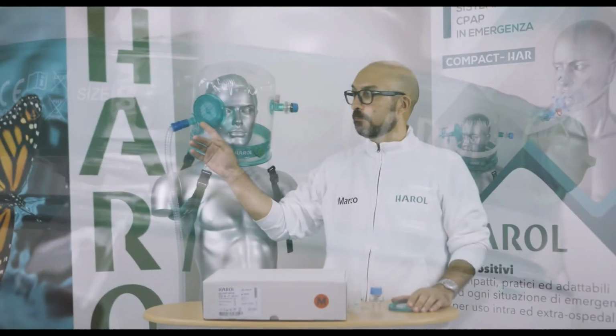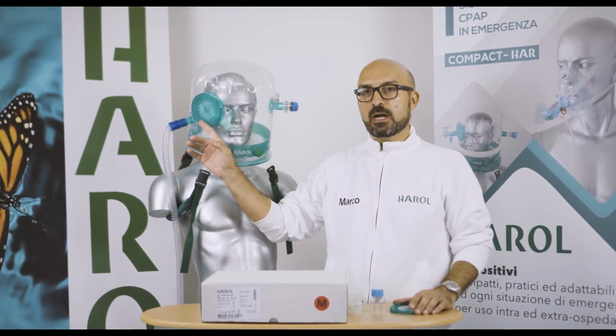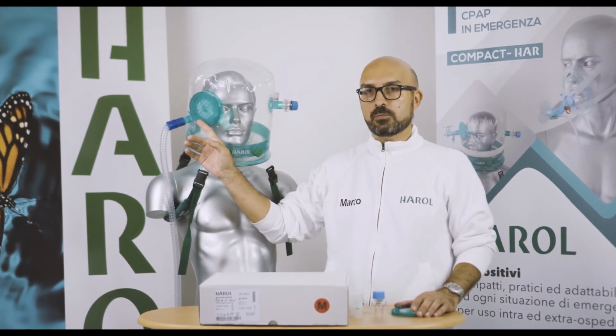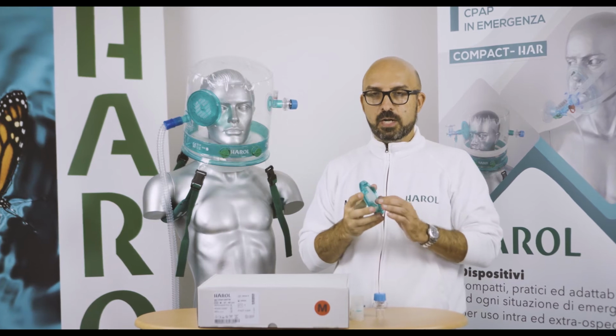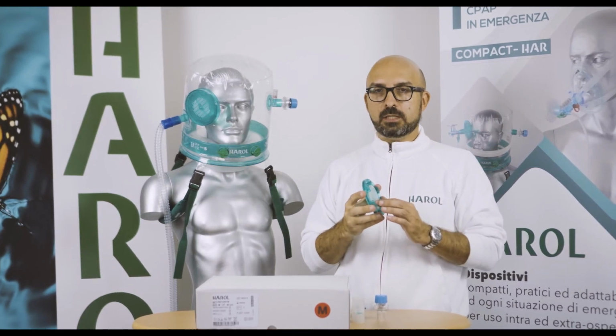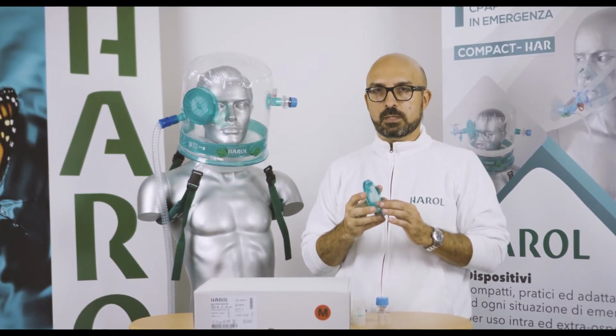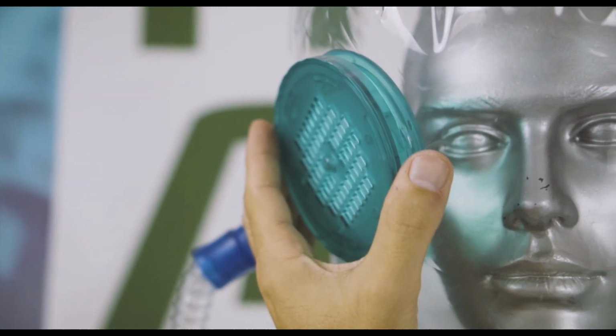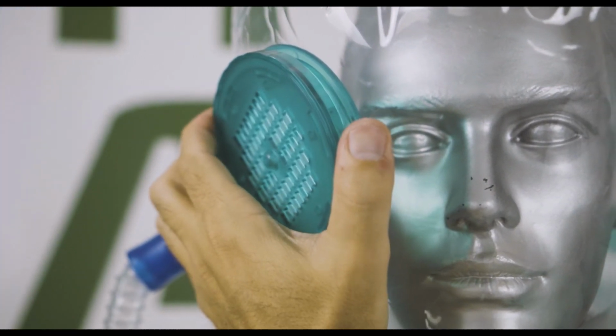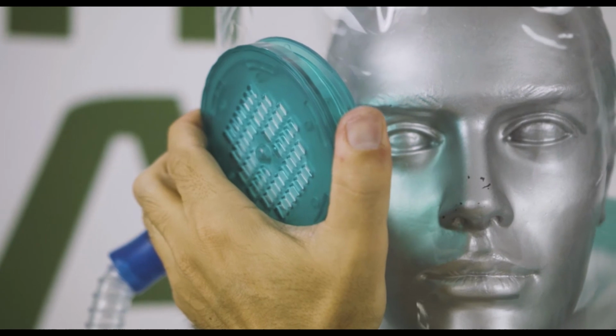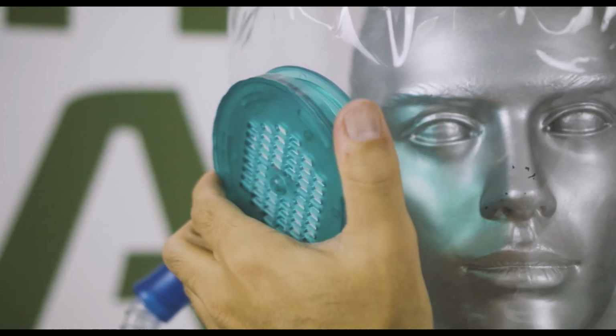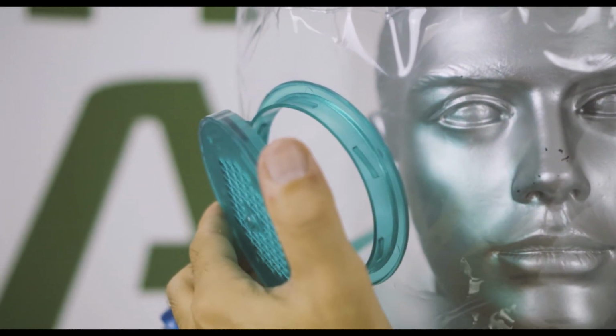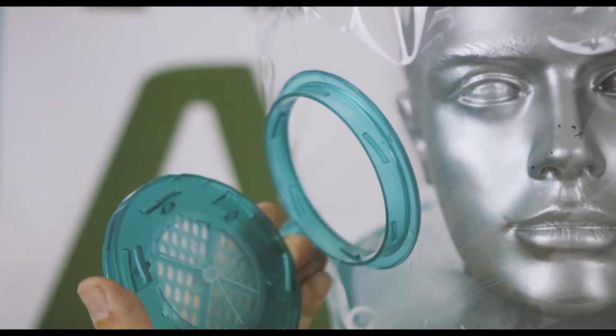The 1 Harol helmet is equipped with a side access port, which allows routine operations to be performed during therapy without the need to remove the entire helmet. On the access port is placed a bidirectional anti-asphyxia valve. This valve automatically closes when the helmet pressurizes and opens automatically when the pressure inside the helmet falls below 2 centimeters of water, without any operator's intervention.